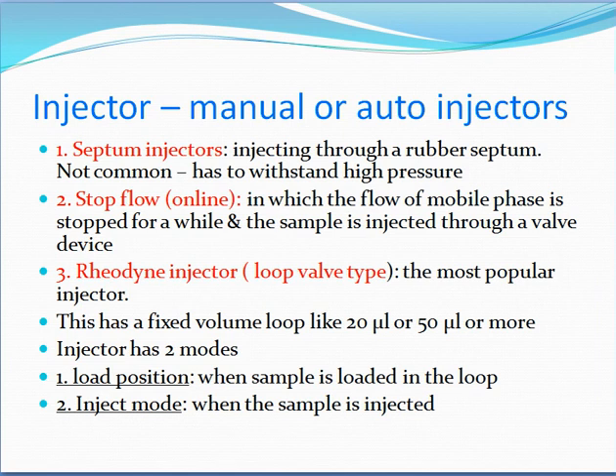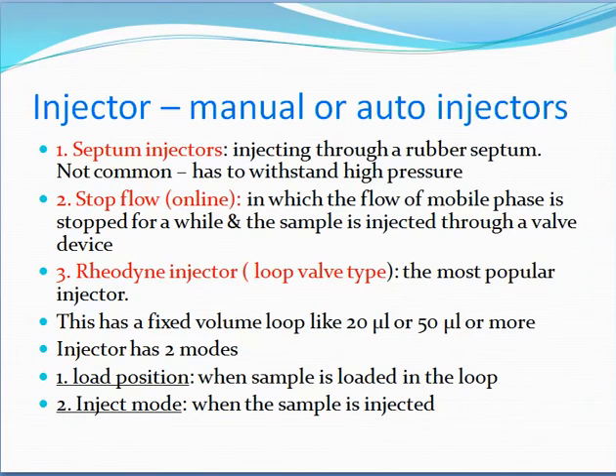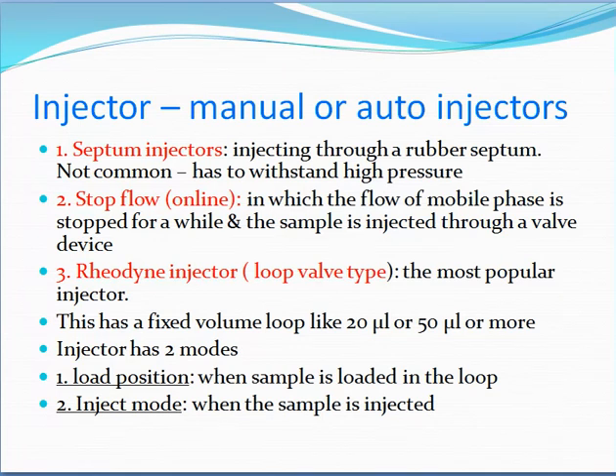The injector can be manual or auto. Types include: the septum injector, where the sample is injected through a rubber septum — not common, as it must withstand high pressure; and the stop-flow injector, where the flow of mobile phase is stopped and the sample is injected through a valve device.